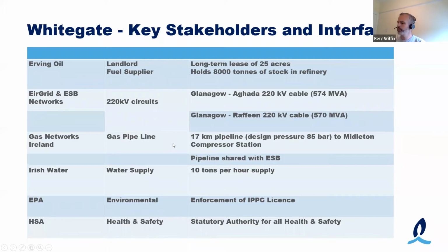On the gas network side, we're connected to the mains gas network. I think it's designed up to 85 bar pressure, but typically it's down around 58, 60 bar in Cork, and that's up to the Midleton station. I'm sorry, go back there.